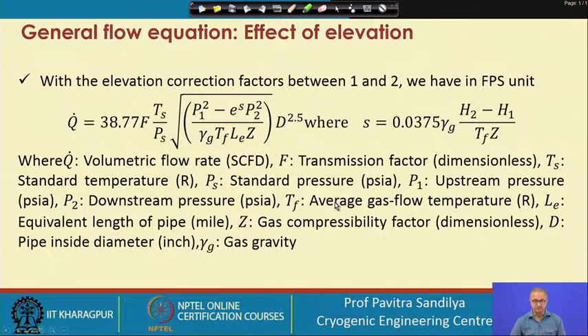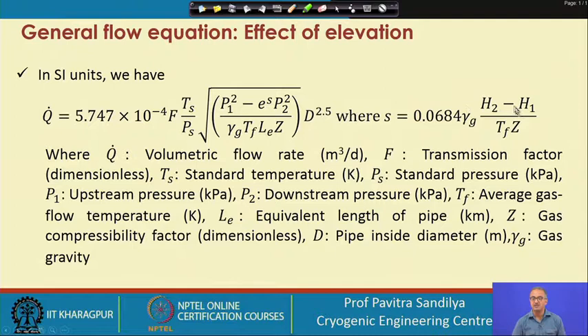The parameter S is expressed differently depending on the unit system. In FPS units, the outlet pressure has a modification due to elevation, and this modification becomes unity when there is no elevation effect. H2 and H1 are the elevations at the outlet and inlet respectively. A similar expression for S is given for SI units, where both the constant for Q and the constant for S change.